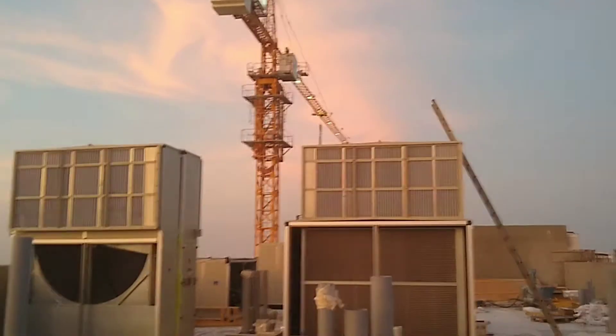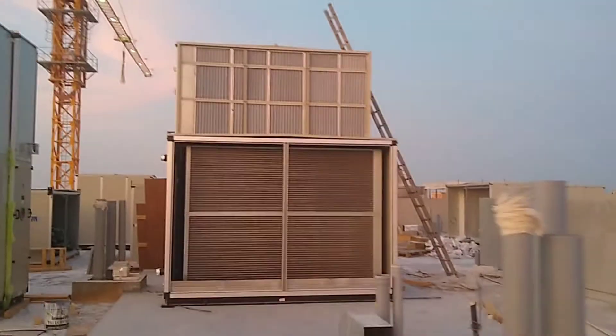Before ending this video, I'll give you a conclusion. This is the heat recovery unit, and this is the blower — sorry, this is the cooling coil operating system. Behind the cooling coil there is a heat recovery wheel, the same thing I showed you before, and the return air will connect here.